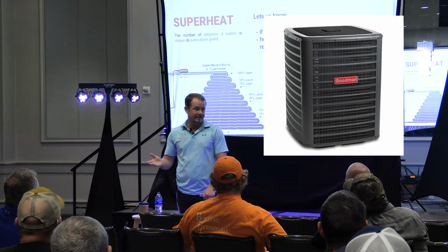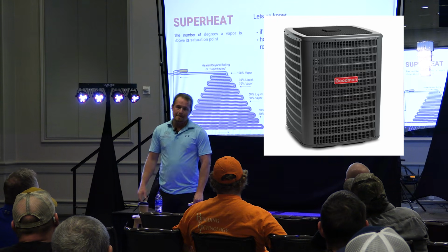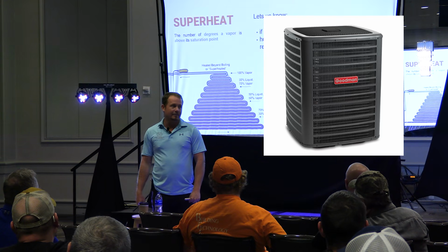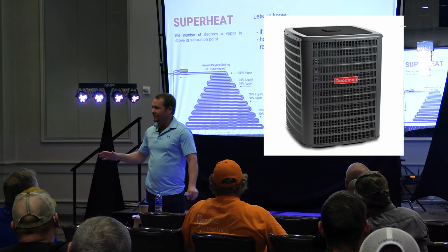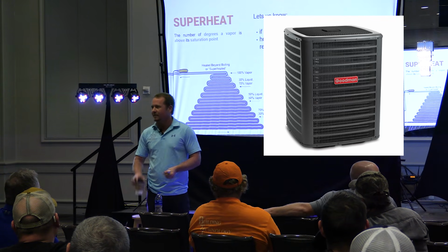You know, you've seen these, right? It's got the liquid line dryer inside the condenser. Those happen to be the ones that plug up all the time too. Might have to do with the fact that Goodman installers are a little different breed, but we won't talk about that. Anybody here sell Goodman? Just kidding. I'm just kidding. We sell Goodman. Nothing wrong with the equipment, just the installers.